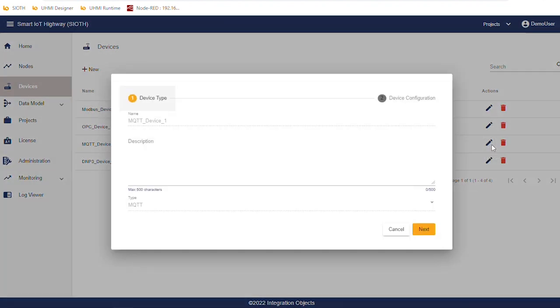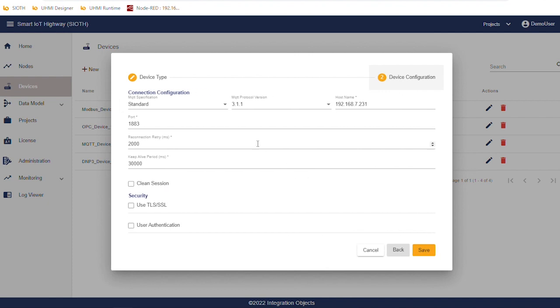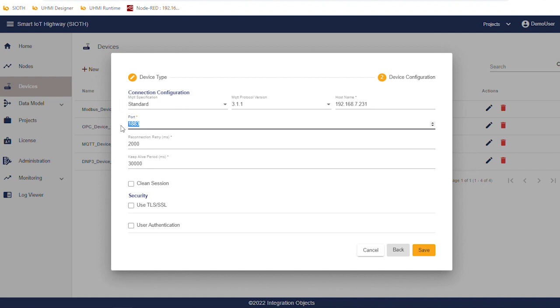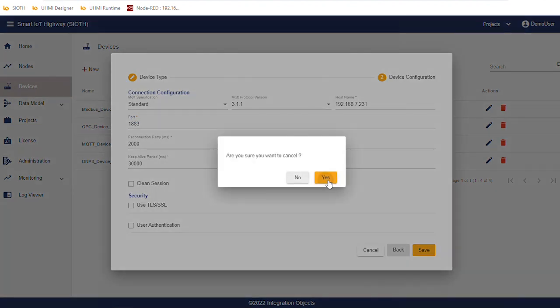Now, we will see the MQTT device configuration. It's a standard MQTT. SIOTH supports also Sparkplug. Here we configure the MQTT broker host name and port. We can also configure the MQTT security using TLS, SSL certificates or user authentication.